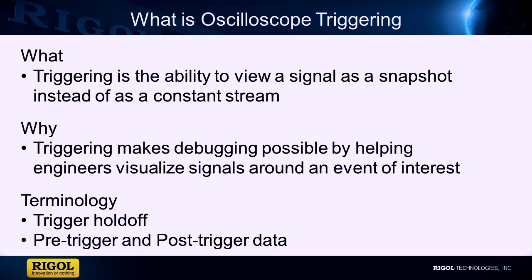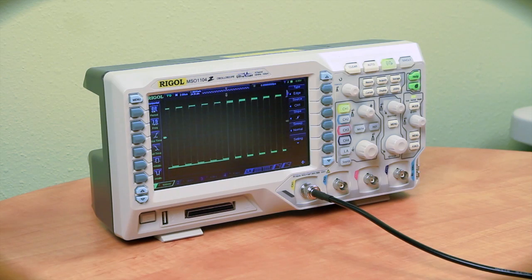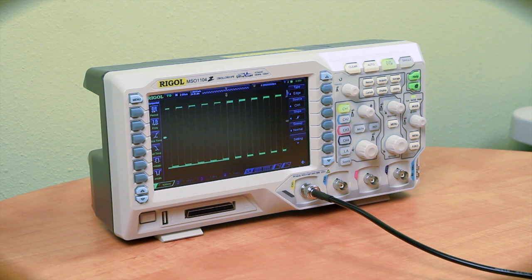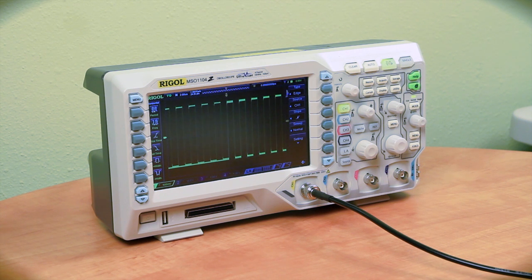There are several important settings to discuss before we discuss the variety of trigger methods. First, trigger holdoff is a setting used with many of our trigger types. This sets the minimum time between two triggers. This is used to make sure the instrument doesn't trigger on an unwanted signal between the trigger events we want to capture.